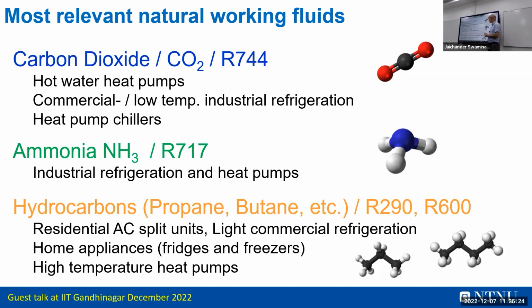Heat pump chillers, I will come back to that - that's what we want to demonstrate in India, in hotels. In a hotel, you need cooling for the rooms, for food and everything, and you need hot water. People take showers all the time, and the spa facilities get bigger and bigger. It's limited how much solar power you can put in based on the specific demand. So that's where a CO2 heat pump chiller makes very much sense. I will show you a picture later on.